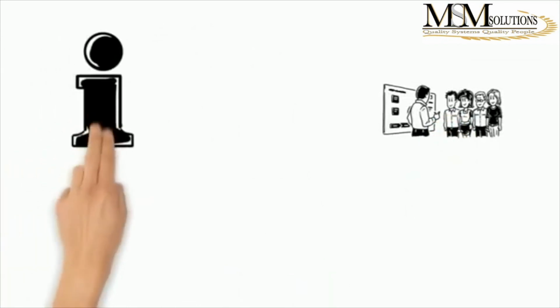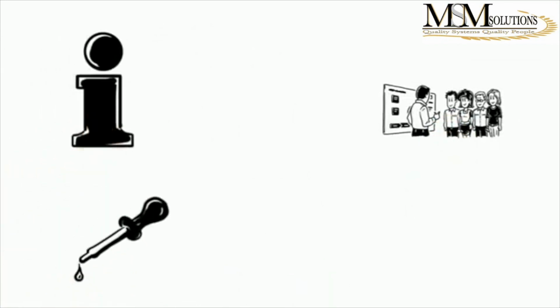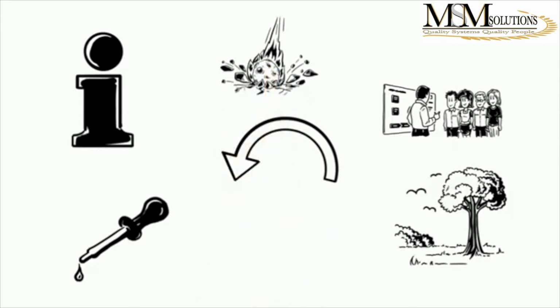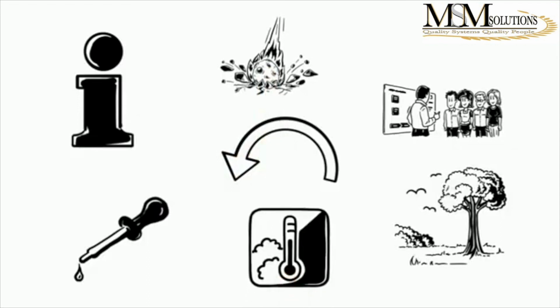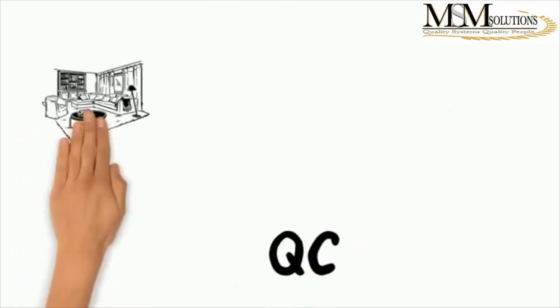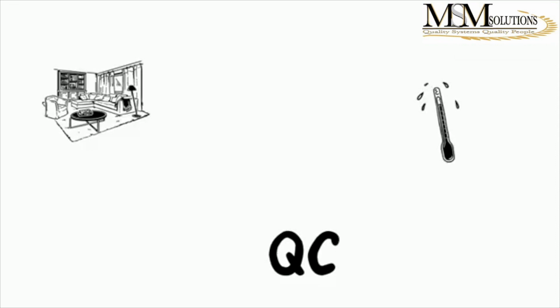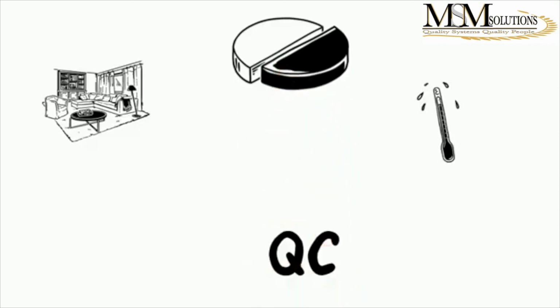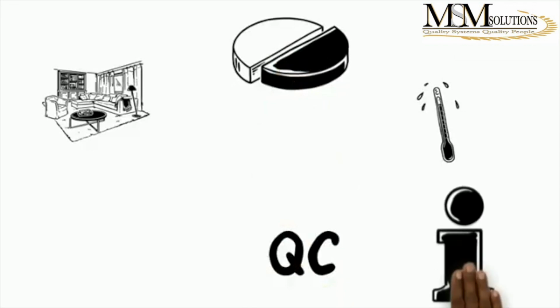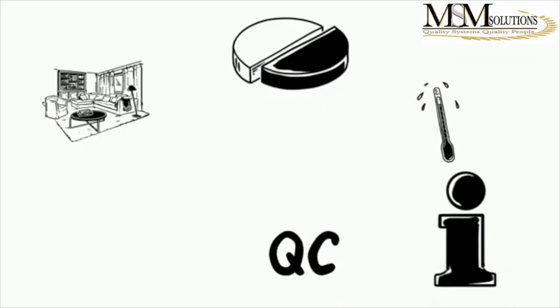So those kind of information, because this is one sample that's been properly prepared, it has one value, so any changes gives you information in terms of, okay, what are we looking at? Other things like impact of changes on the method. It could be a simple impact as environmental changes. Maybe the method you're doing is temperature sensitive, sensitive to room temperature, you can then see that from your QC result. That, oh, if I use it in a room that is at 30 degrees, it operates differently, or it gives me a different result compared to when I use it at 20 degrees. That kind of information is what a QC can help you with.